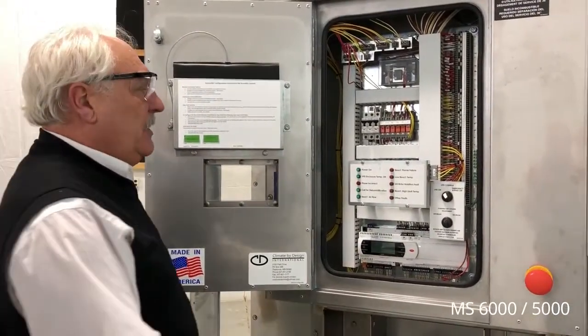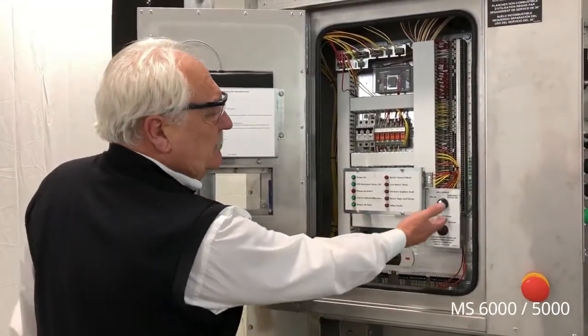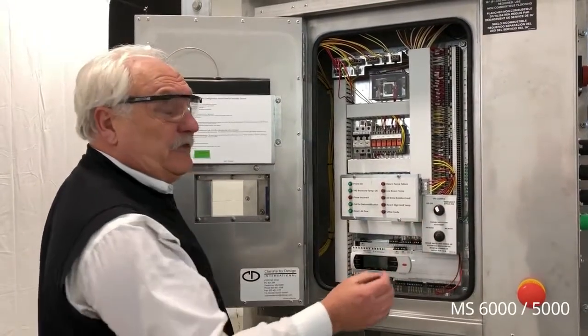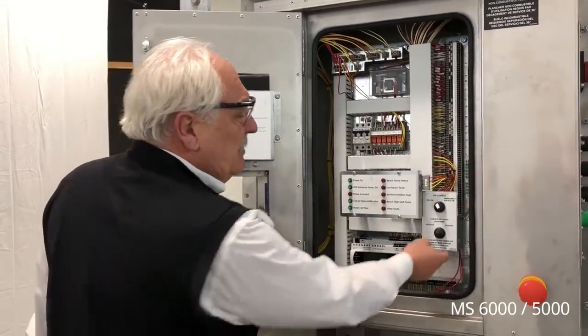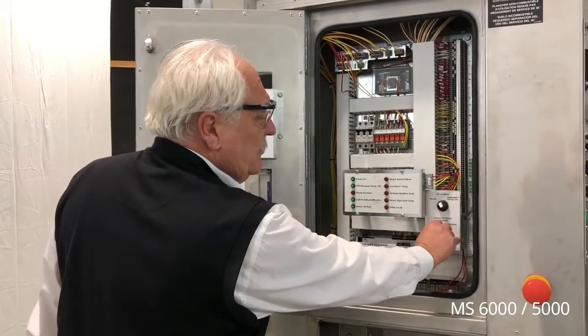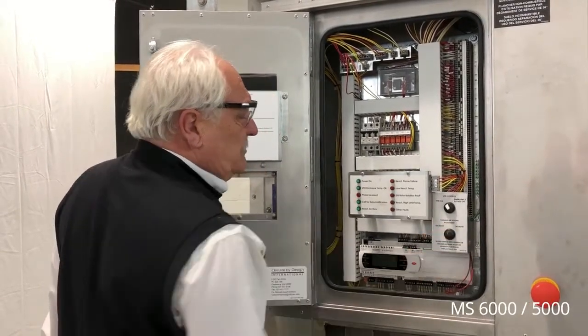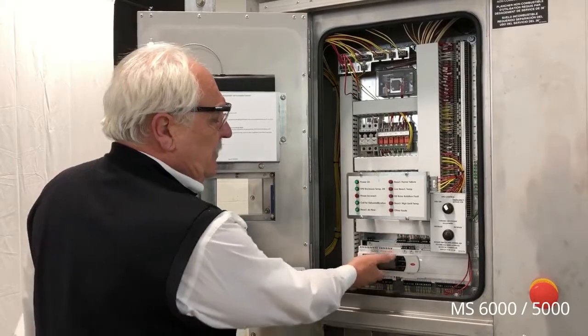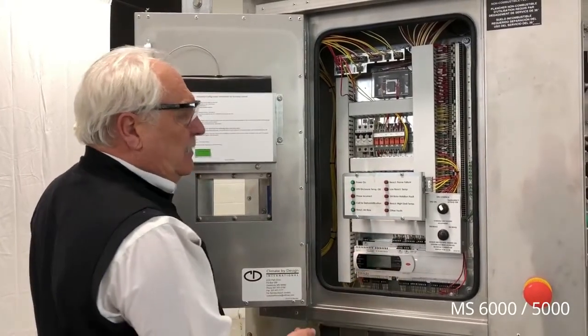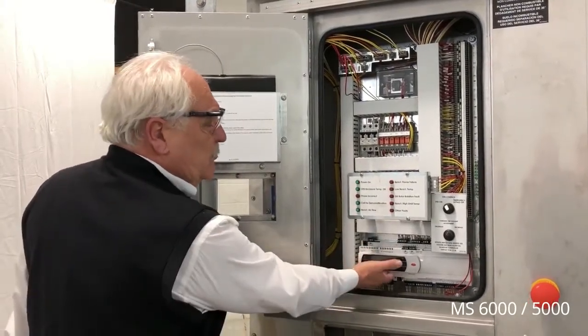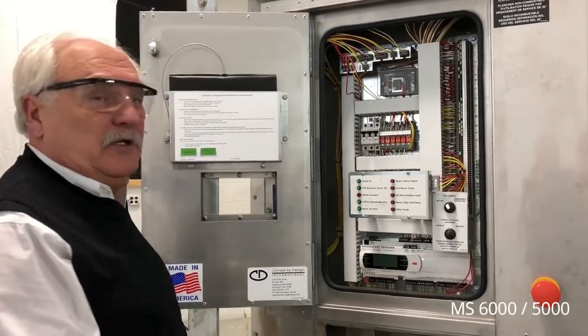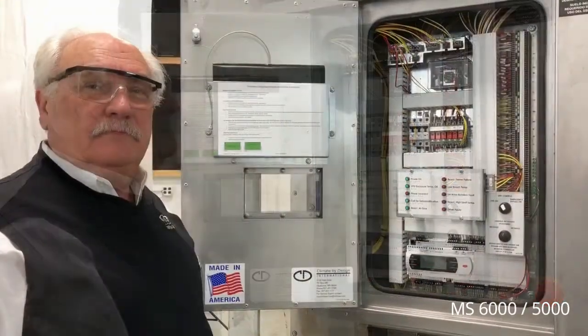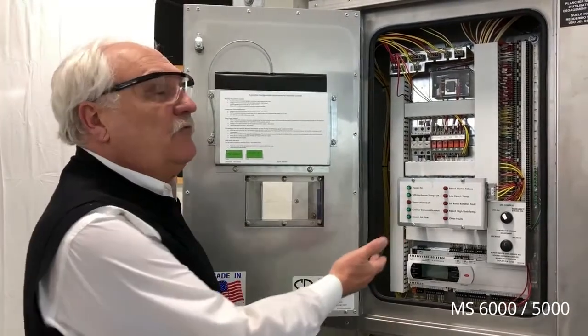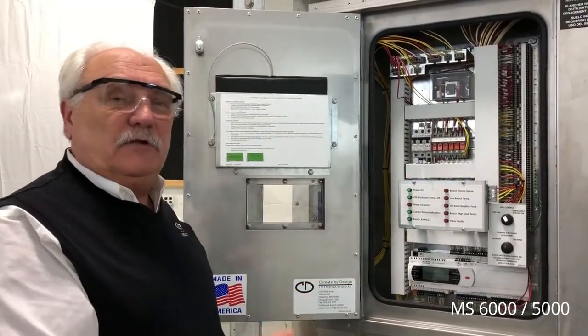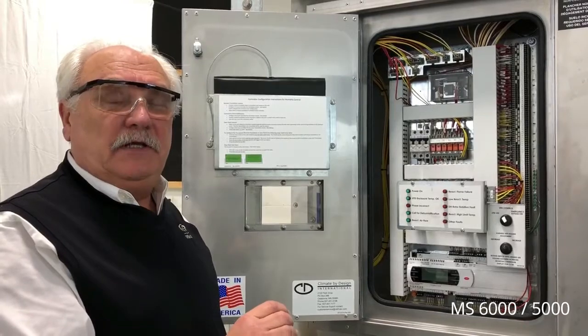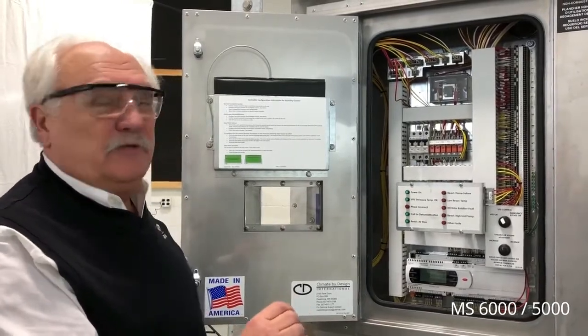Inside the low voltage panel we have the indicating lights. We also on this unit have the optional variable frequency drive. We can adjust the volume of the dehumidifier flow by adjusting the drive. The SCFM is indicated on the Carel controller, which houses the brains for the operation and the timing of the units. Please note that this is a low voltage panel, 24 volts or less, so there's no PPE equipment normally required for servicing this area.